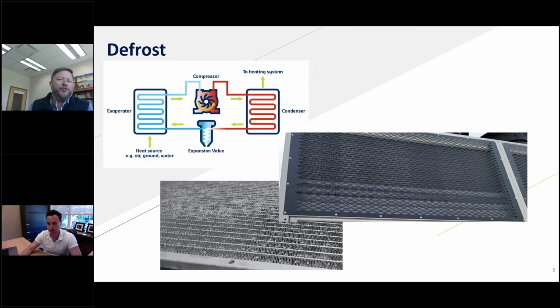So the refrigerant diagram that maybe nobody saw that I was referencing is in the upper left-hand corner. The two pictures that I have show different coils. The one on the lower left is a microchannel coil, and you can see how frost is formed there. The one on the right is more of a traditional coil, a tube and fin coil. In both cases, you're going to see frost or ice formation on the coil if you're operating at lower ambient temperatures, and you're going to see it happen sooner as we have higher relative humidity at those lower ambient temperatures. Okay, so that is something that we have to account for in our design.